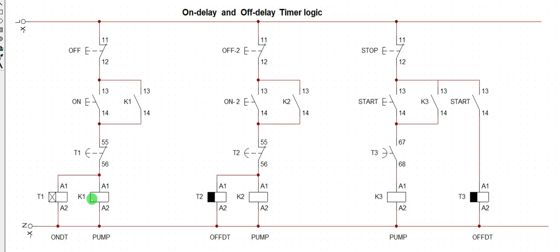Okay, so if you're expected to use this logic, this is the relay that you use, the on delay timer. You will not use that same logic for off delay. The logic of off delay is going to change, and this is the logic for off delay. I repeat again, the coil of the off delay timer must be de-energized for the subject of the appliance you want to control to be fulfilled. So before the off delay timer starts counting, you must de-energize the coil.